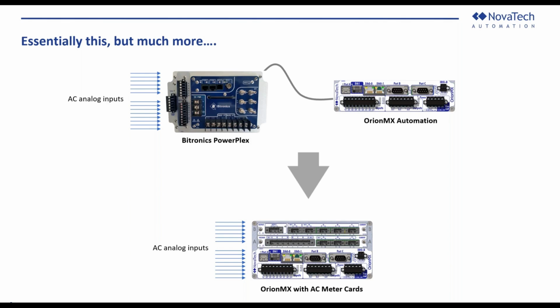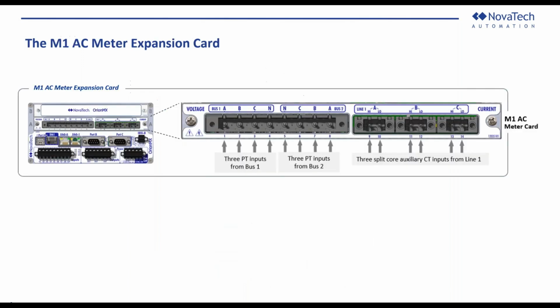And you understand how Bitronics instruments work. There's AC analog inputs and measurements are made based upon basically three-phase currents and three-phase voltages. Hundreds of values are derived from there, power measurements, energy measurements, etc. So we repackage that, and there is an optional display that you can put on there. We repackage that into a card that fits into the OrionMX. Here's what the card looks like. The 3 PT inputs from bus 1 and bus 2, and 3 split core auxiliary CT inputs from line 1. And we use the term auxiliary in that that implies that it's connected over the existing CT circuit, which would nominally be 5 amps.